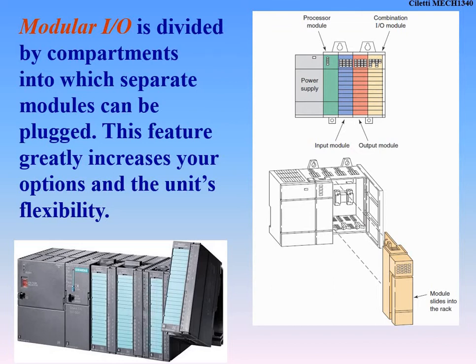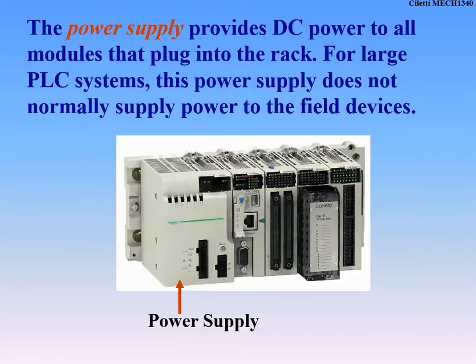Modular IO allows the PLC to keep expanding and adding more inputs and outputs. Fixed IO can only handle a set number, say 128 inputs and outputs. For the power supply — all PLCs have to take 120 volts from the wall, rectify it, and convert it to 24-volt DC because all of our IO runs on 24-volt DC. Power supplies are sometimes attached to the PLC and sometimes separate, depending on the unit.